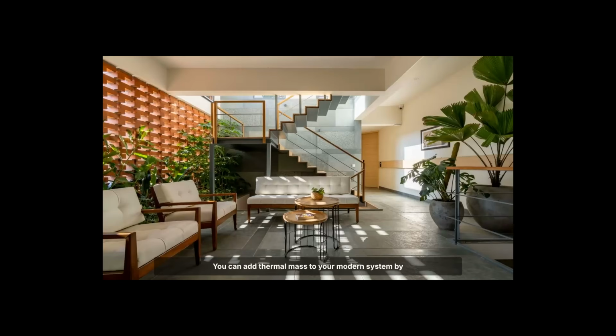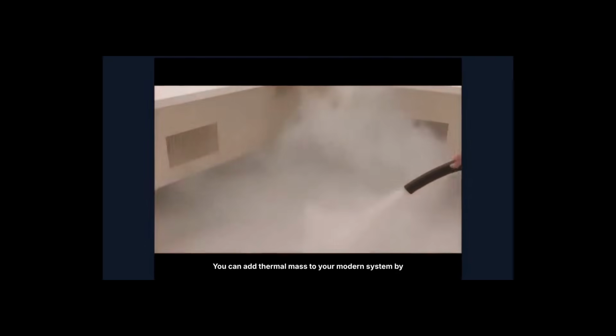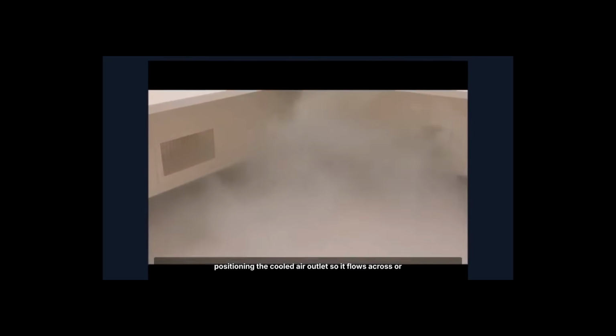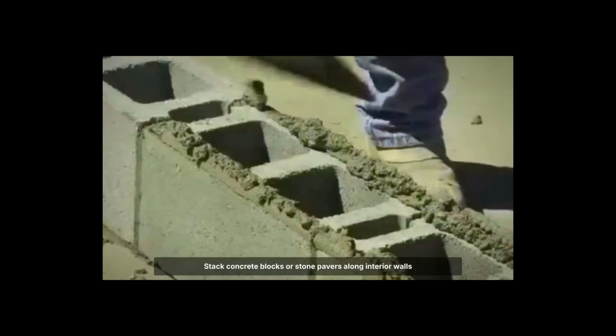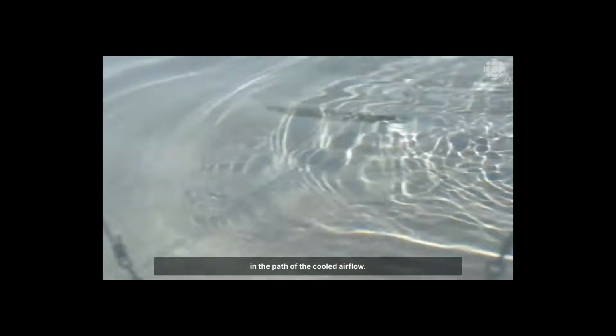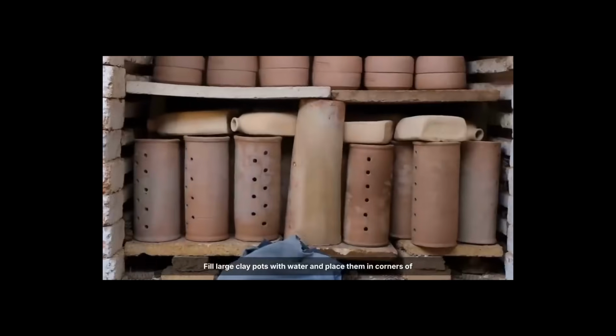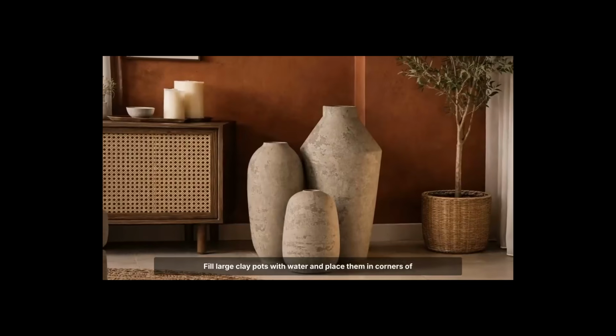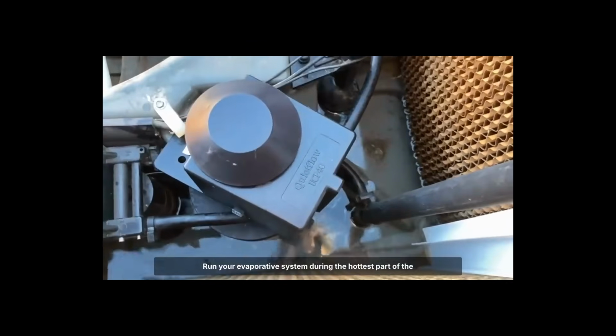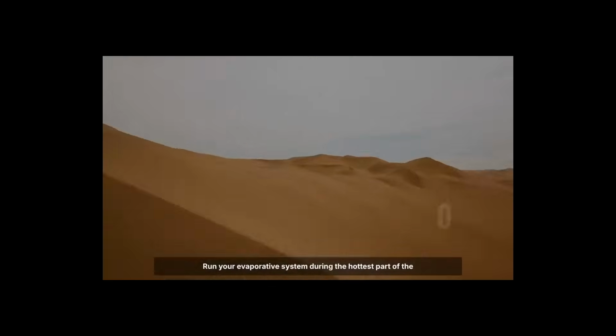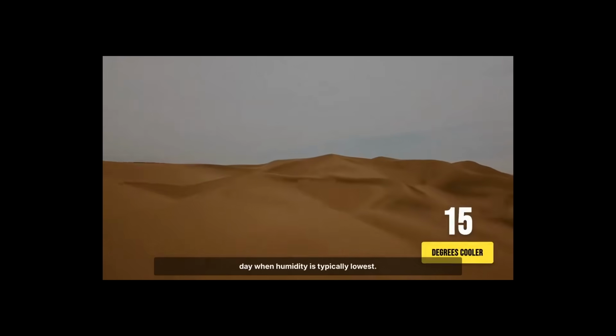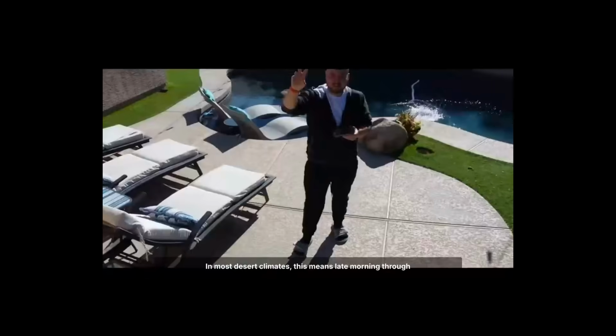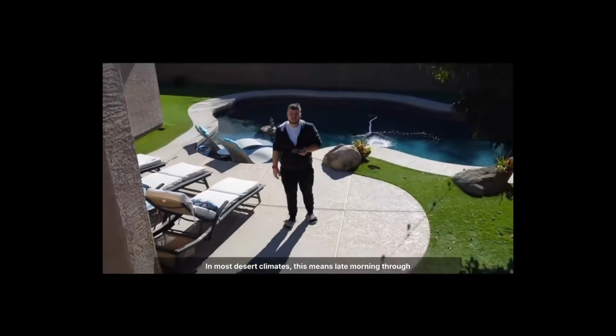You can add thermal mass to your modern system by positioning the cooled air outlet so it flows across or through dense materials. Stack concrete blocks or stone pavers along interior walls in the path of the cooled airflow. Fill large clay pots with water and place them in corners of the room. Run your evaporative system during the hottest part of the day when humidity is typically lowest. In most desert climates, this means late morning through late afternoon.